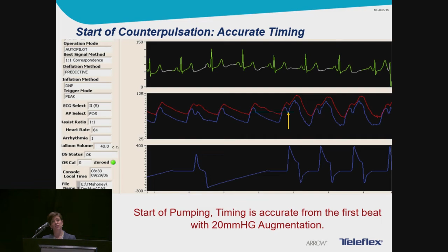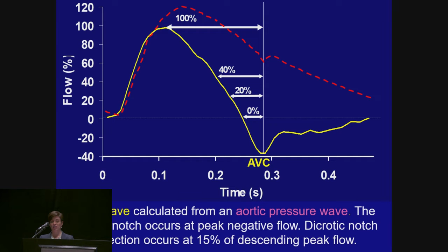Here, this is an example of the aortic flow calculation from our WAVE algorithm. WAVE stands for Windkessel aortic valve equation. And the flow is calculated from the arterial pressure waveform as it occurs, so it is in real time. Now, peak flow always occurs before peak pressure, and we know the aortic valve closes at the lowest point of flow after the peak. By knowing how long it takes to inflate the balloon, we can use a percentage of the descending flow to start inflation before the aortic valve closes and have augmentation pressure rise as the aortic valve closes.